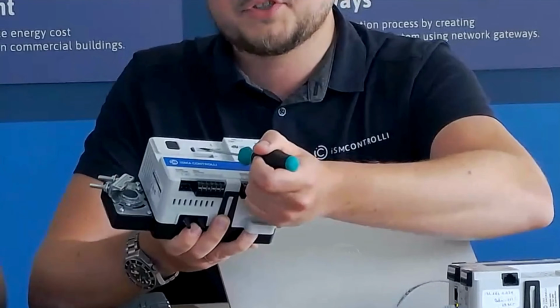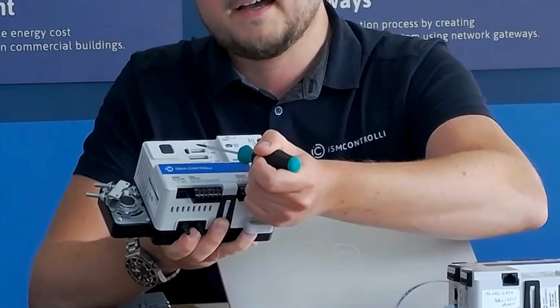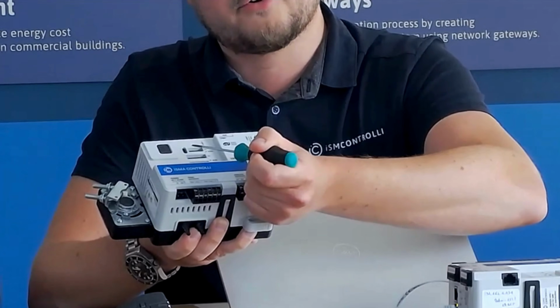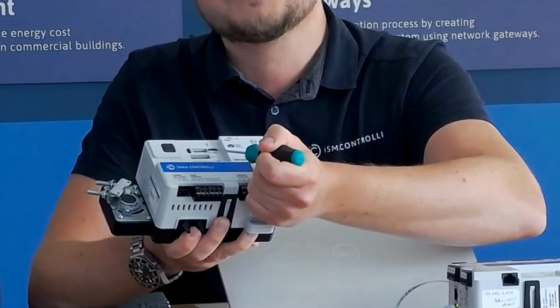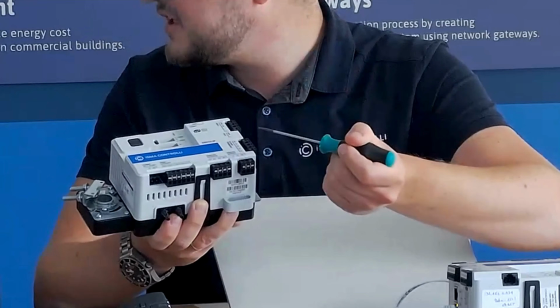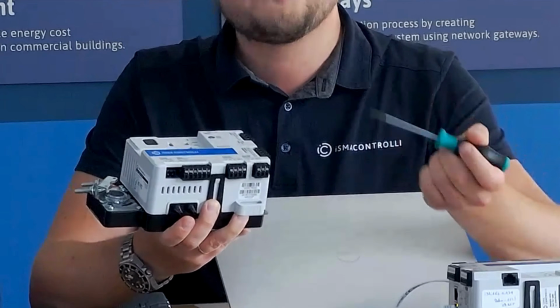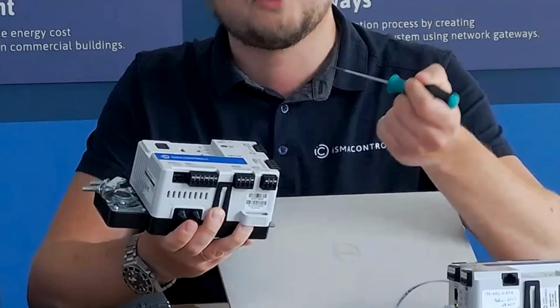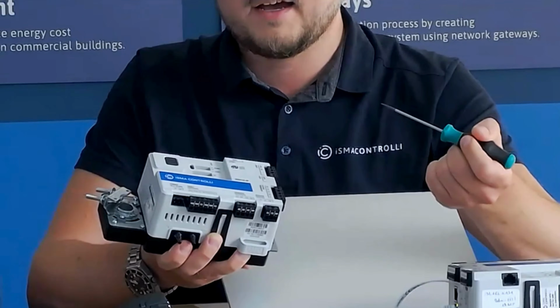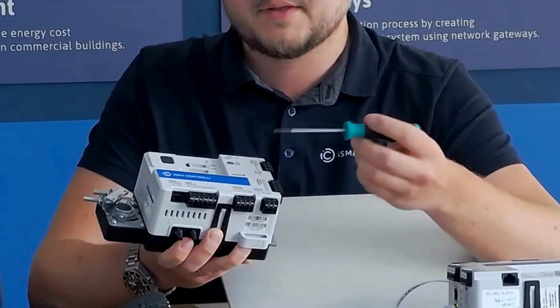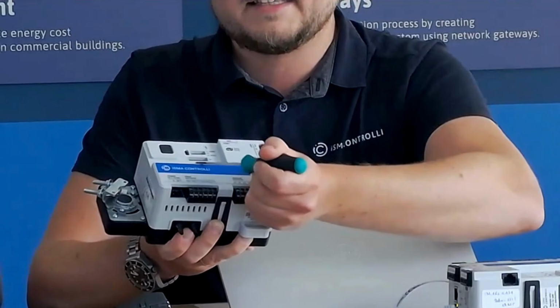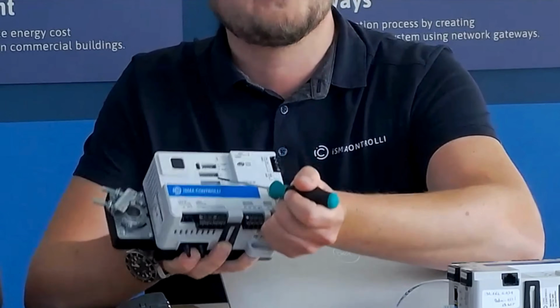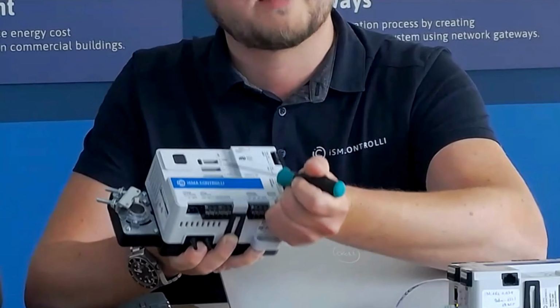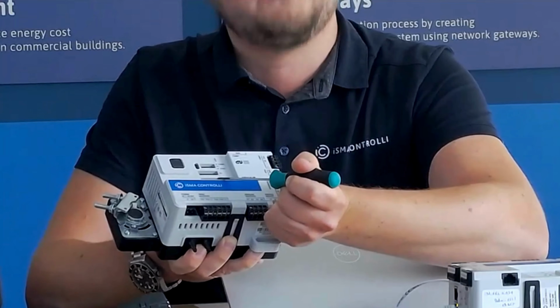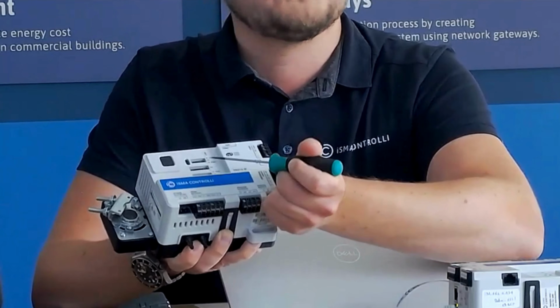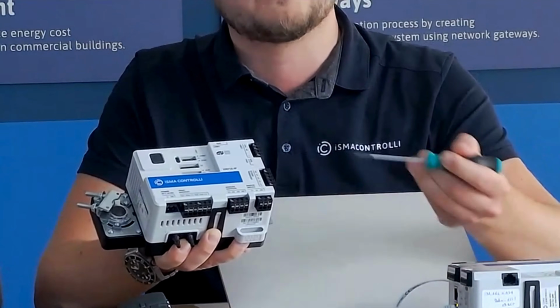So the first dip switch will allow you to set the imperial or metric units, and also bring the controller back to the default settings. Even if you have made some changes to the controller, you can always bring it back using one of the switches. And dip switch number 3 will give you all the capabilities of the application configuration. By default, it is in a BMS mode, which will allow you to configure it with our tools.